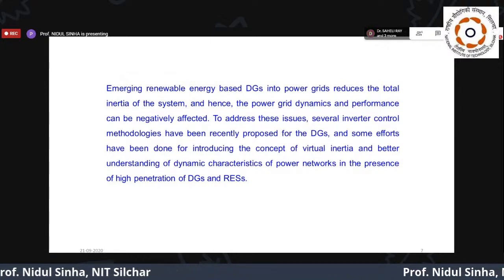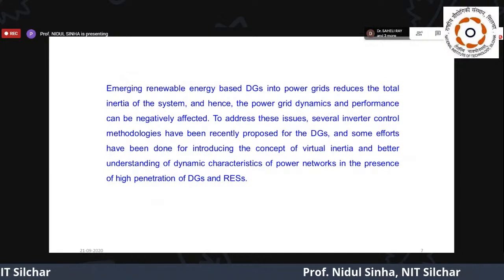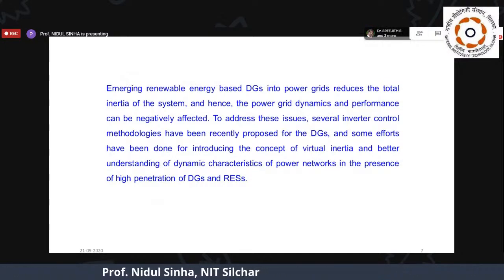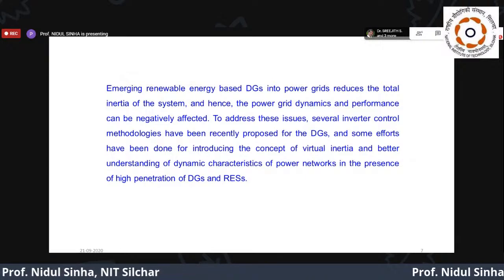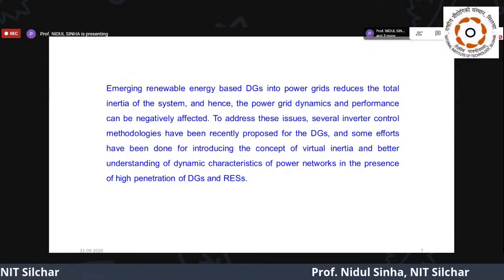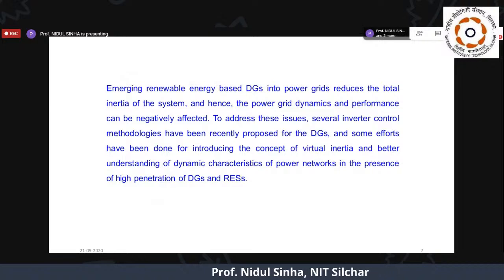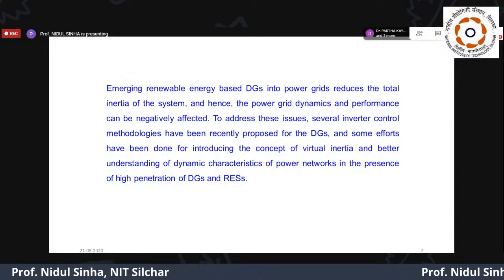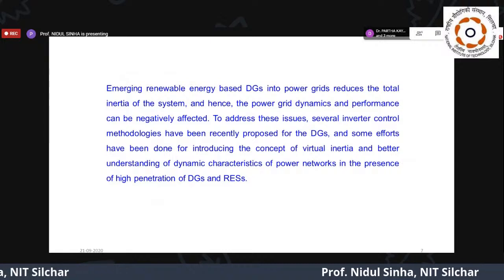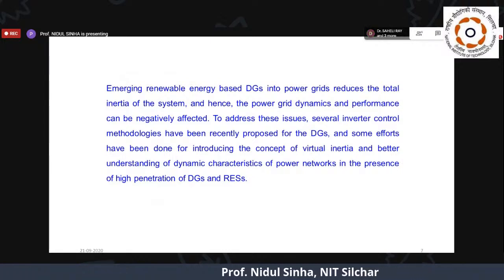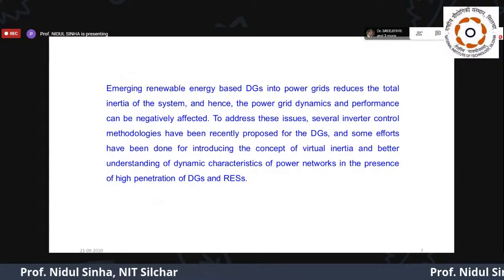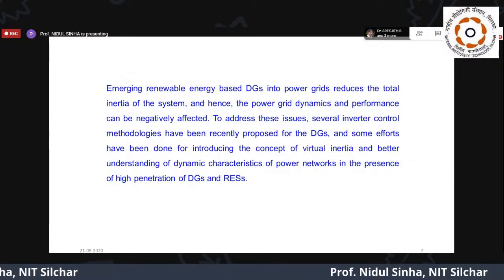Nowadays most generators are provided with static excitation systems, electronics based excitation systems. In earlier days, it was different — you'd have a separate generator connected with a DC generator to supply DC to the field winding. Now we go for all static excitation systems, and ultimately the AVR loop with a static excitation system becomes very fast responding.